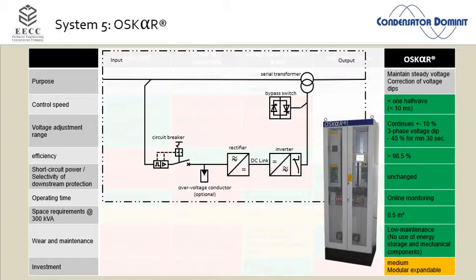So what we said is, we go into bypass as fast as we can, and that's why we introduced more or less 2 mechanical, 1 IGBT and 1 thyristor bypass, which are independent in control and in technology. That was very important for us. If I have a failure on my microprocessor, this bypass is totally independent. So at least we must have 2 software failures in 2 totally independent microprocessors. We don't want to leave everything on 1 microprocessor.